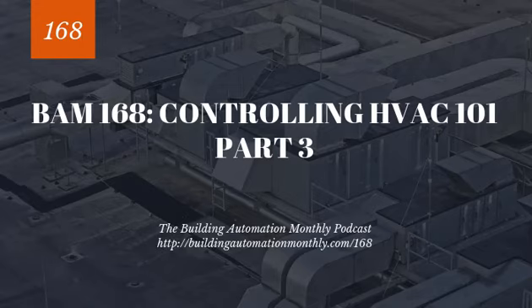Because now we realize the reason we are using a partial load chiller is because it's more efficient. And the reason we have partial load is because either our GPM or our delta T has varied. So those are the two variables that impact the tonnage of cooling required by our building systems.